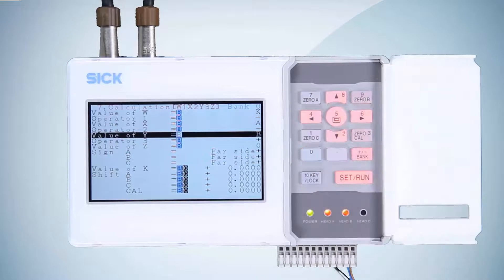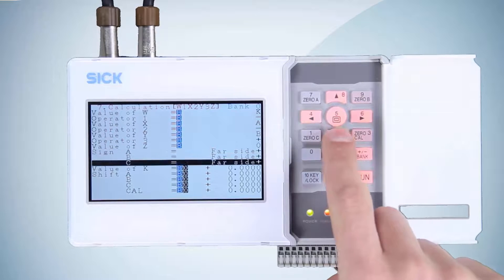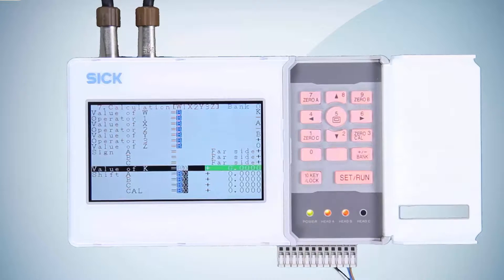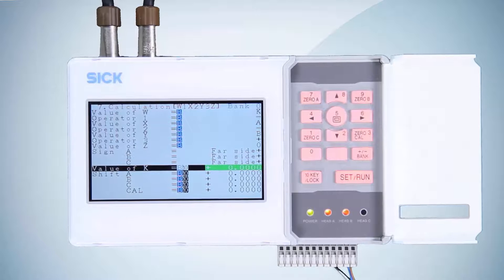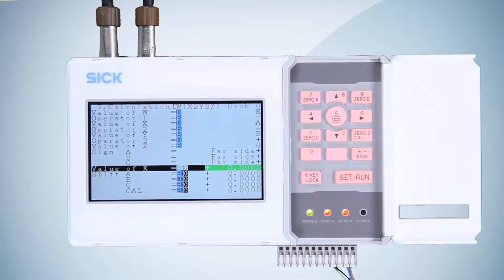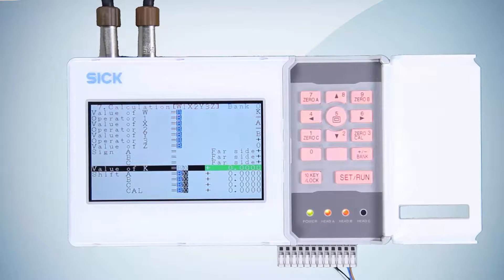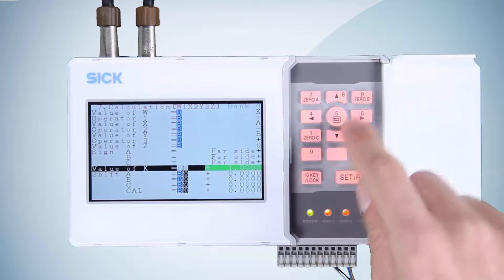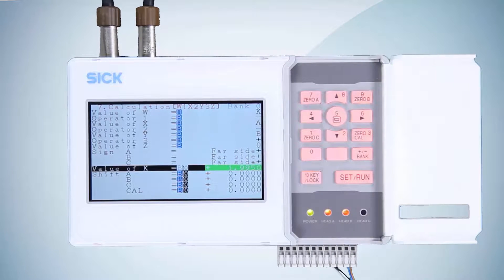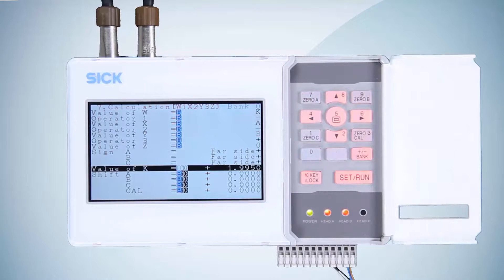Now go to value of K and press the 10 key/lock pushbutton to enter a value using the number keys. Enter the reference value, in our case 1.9950, and press the number 10 key/lock pushbutton again to finish entering the settings.